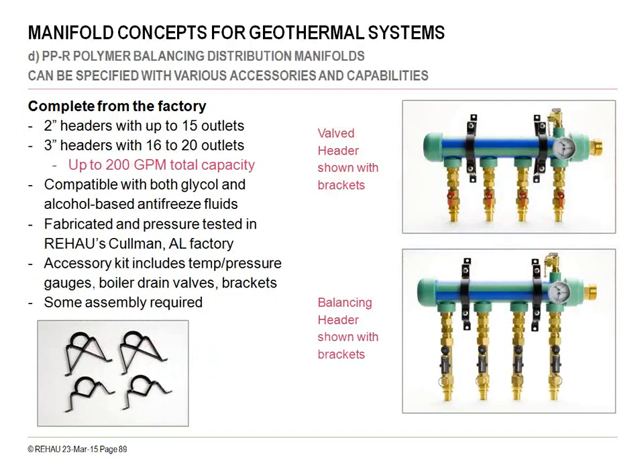We fabricate these also at the same plant where we extrude and fabricate the U-bends of the PEX-A down at our plant in Alabama. We fabricate these all the way up to 20 continuous drops, 10 GPM per circuit, or if you will, up to a capacity of 200 GPM in a 20 drop header set. These would have flow gauges. In this case, they're polyethylene flow gauges with a bypass pin to get a reading.